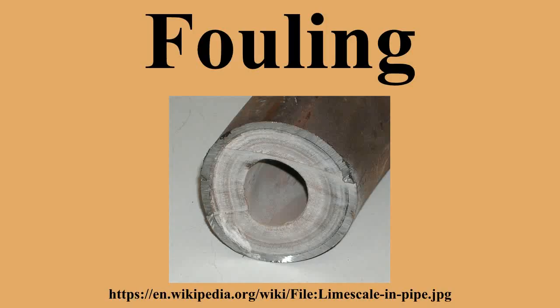Components subject to fouling. Following are examples of components that may be subject to fouling and the corresponding effects of fouling. Heat exchanger surfaces: reduces thermal efficiency, decreases heat flux, increases temperature on the hot side, decreases temperature on the cold side, induces under-deposit corrosion, increases use of cooling water.